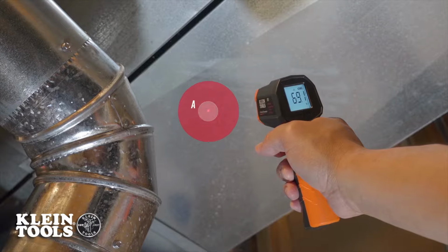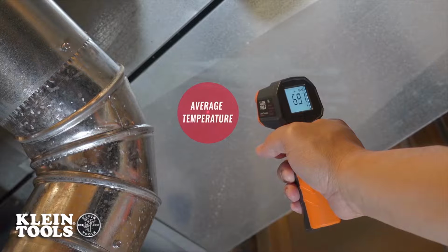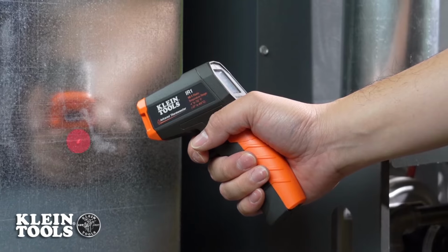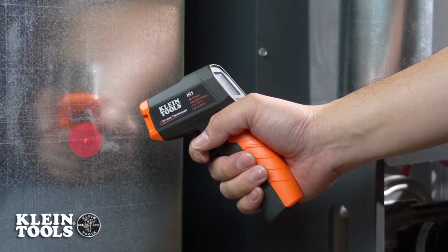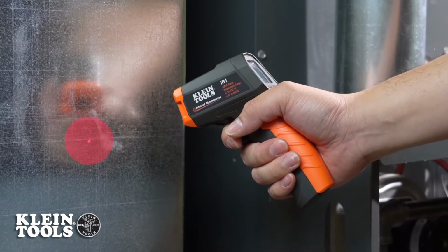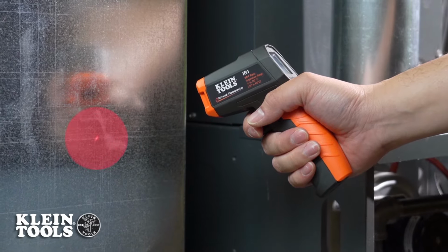To use an infrared thermometer properly, you need to know that unlike other types of thermometers, IR guns don't measure the temperature of a single point. Rather, they display the average temperature of a circular area centered on the unit's aiming laser dot, and the size of that circle depends on how far away the temperature gun is from the target. Much like shining a flashlight on a wall, the circle is smaller if you're closer in range and larger if you are farther out. How big is the measurement circle?